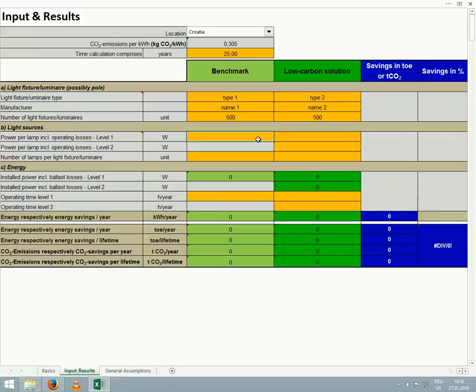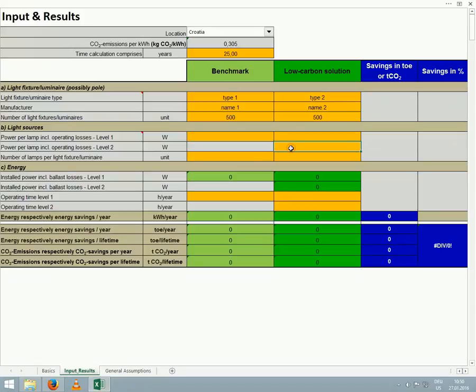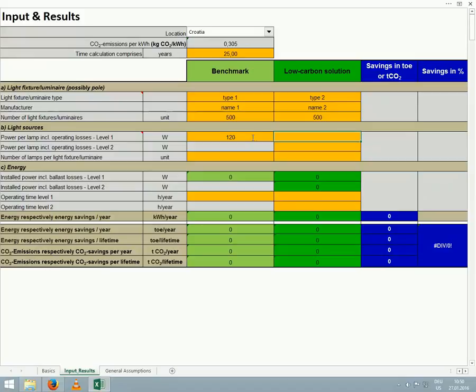Some street lights are dimmable, which means they have two different operating levels of power. We have provided fields for you to enter this data if it is available to you. Using our example from Croatia, we enter just one level of 120 watts for the benchmark, and we enter two levels for the low carbon solution, 103 watts for level 1, and 50 watts for level 2.